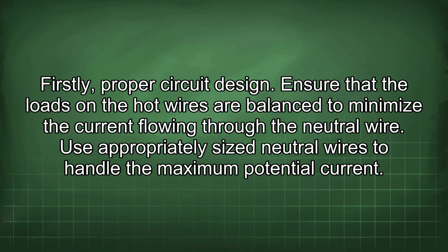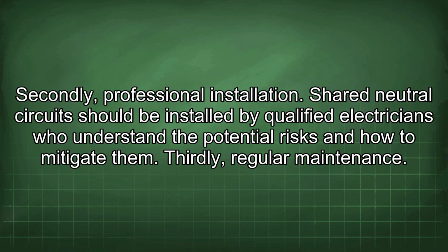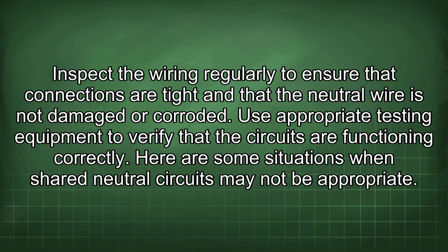Ensure that the loads on the hot wires are balanced to minimize the current flowing through the neutral wire. Use appropriately sized neutral wires to handle the maximum potential current. Secondly, professional installation. Shared neutral circuits should be installed by qualified electricians who understand the potential risks and how to mitigate them. Thirdly, regular maintenance. Inspect the wiring regularly to ensure that connections are tight and that the neutral wire is not damaged or corroded. Use appropriate testing equipment to verify that the circuits are functioning correctly.